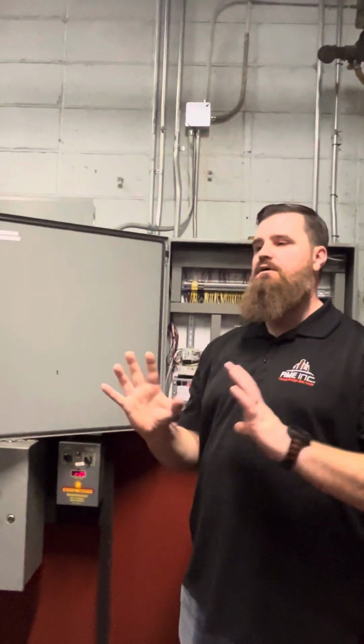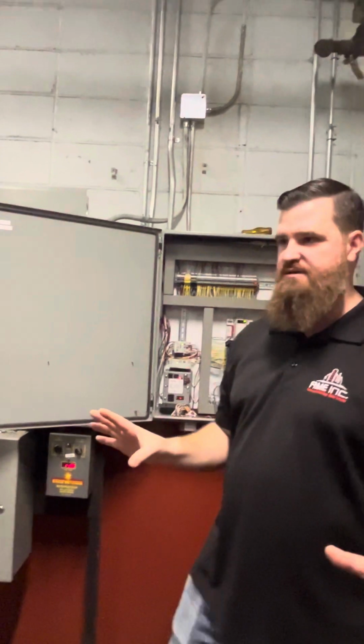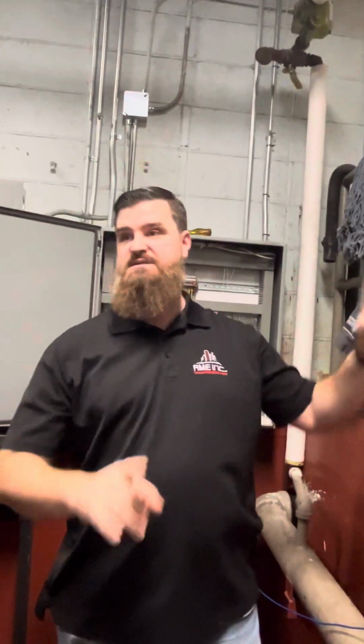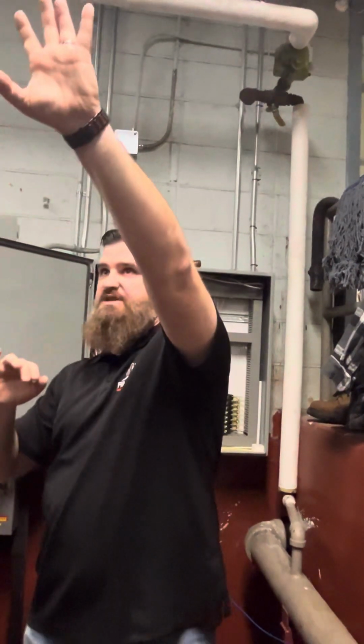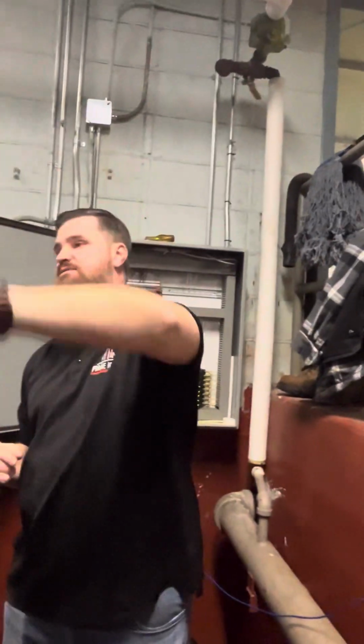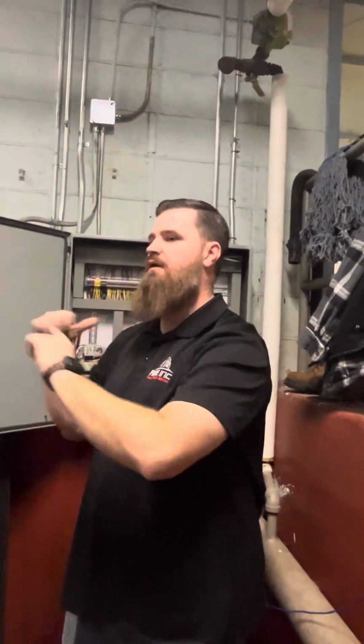I'll even go as far as to say that fan should have been tied some way to some kind of controller other than the BMS to those boilers directly, saying, hey, we're good to go. The fan's running, we've got combustion air coming in, go ahead and fire this thing. But that's how the dampers are right now, because those are connected to the burner and then to whatever that controller is doing, and those need to stay. Each damper for each respective boiler needs to stay with that boiler. It should never be coming back to the BMS.